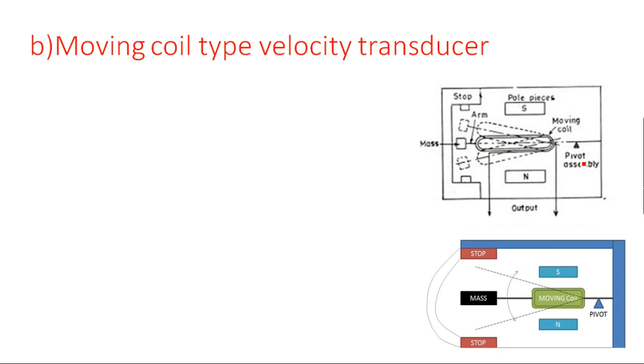The second type is moving coil type velocity transducer. In the first case, the coil is fixed and magnet is moving. In the second case, the magnet is fixed — south pole and north pole are indicated here as pole pieces — and the coil is moving. The coil moves upward 45 degrees and downward 45 degrees. It is fitted to a stop assembly on one side and a pivot assembly on the other side.